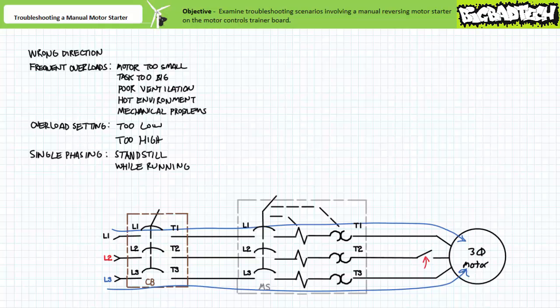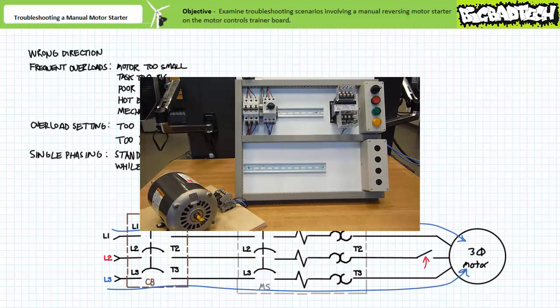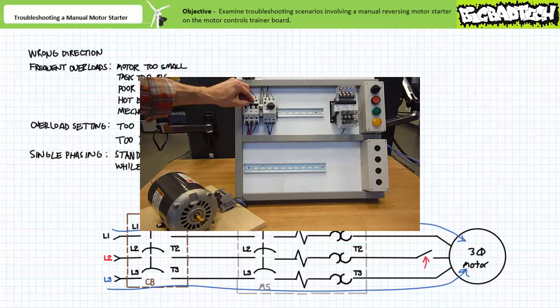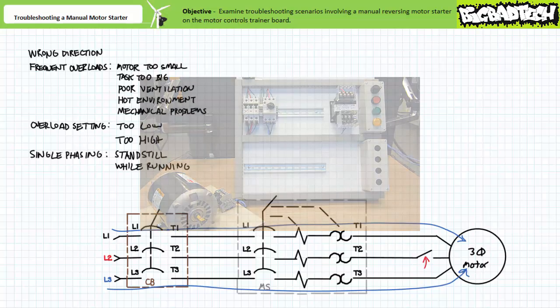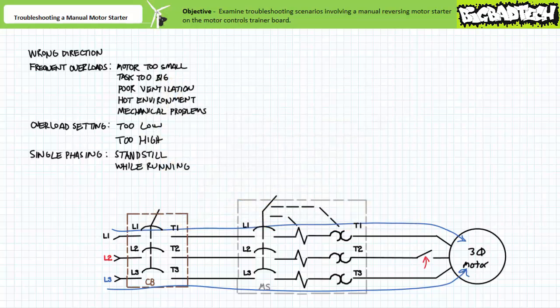Warning, do not try this at home. There are additional circuit protection elements in play. Here's a manual motor starter that I've intentionally disconnected phase L2 between the manual motor starter and the motor. When I close the manual motor starter, the rotor doesn't turn. If you're too dense to know something's wrong, the overload quickly steps in to break it up by opening the manual motor starter. Only the densest of operators would try to start the motor again after observing such an event. However, they do exist and they all work at the same company you do.